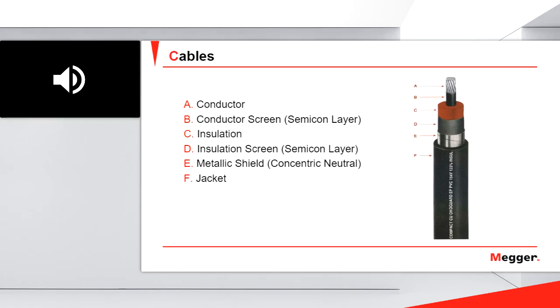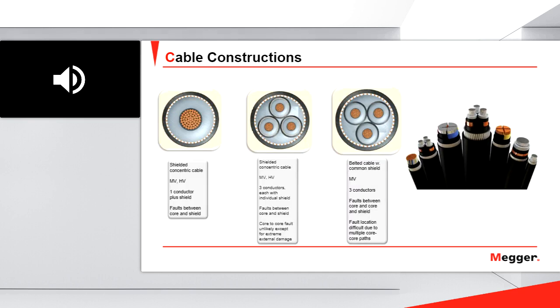So we have different types of insulation, and that is important for fault location. Next, we have the insulation screen, or the second semicon layer. And then we have the metallic shield, or the concentric, of our cable. And finally, we have the jacket of the cable. So this is mostly the one-phase construction of a medium voltage cable. Of course, we can have different cable constructions. Starting from the left, we have the same cable I showed in the previous slide.